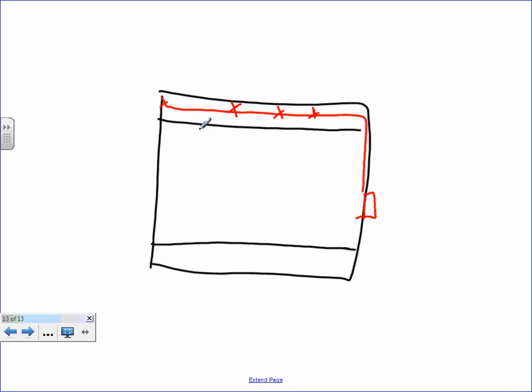We're going to have another, so we've got one pipe. This is a 4-pipe system. Each pipe is a separate zone in the system. So we're going to have one pipe that's coming up in here, and our second pipe coming up here, and that's going to be going down into the drop ceiling. So we're going to monitor in the room. And you can cross zone them, so you can have 2 pipes going each way. You've got 2 pipes here because the room is longer, and those are going to be cross zoned with each other.